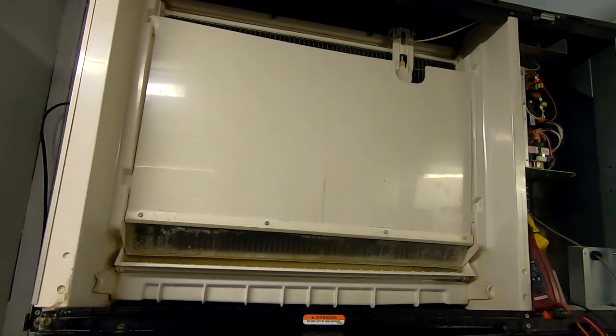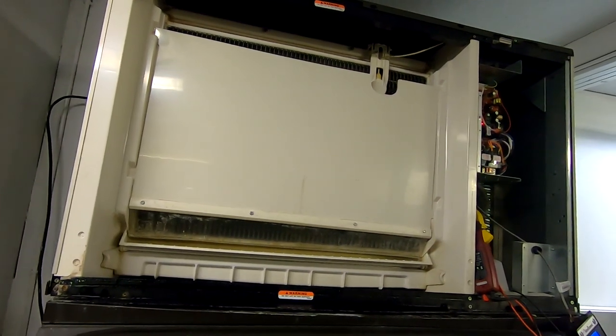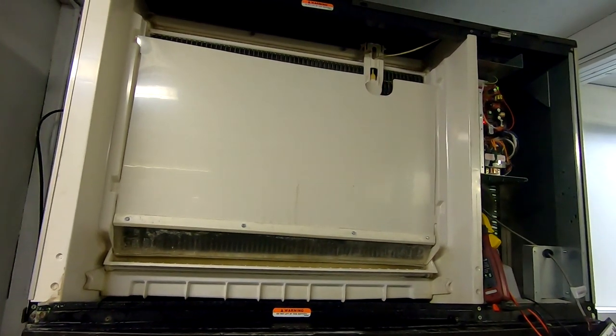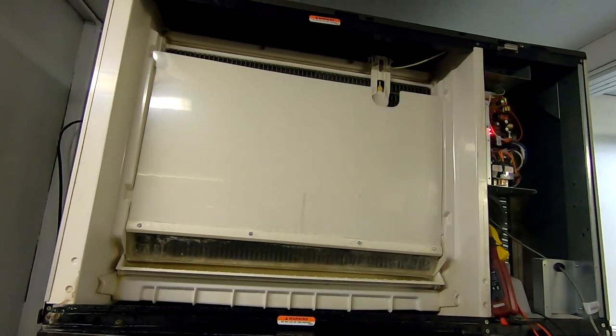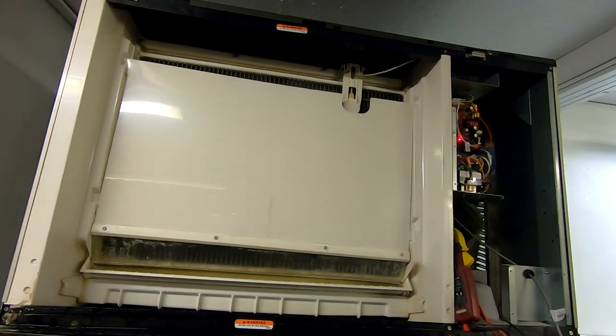The old rule of thumb for the smaller, older machines used to be three and a half. This one here, the Indigo, I think they have another type of algorithm, but originally they wanted three and a half minutes or less. Otherwise it could lock out. So we'll see how she drops here.